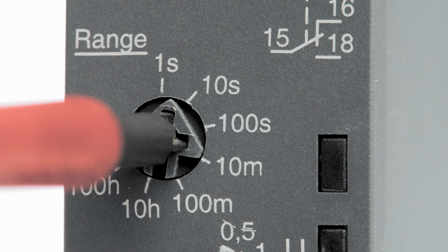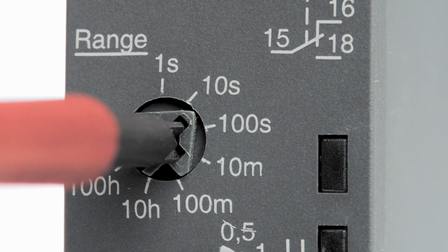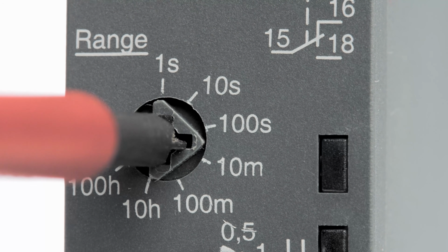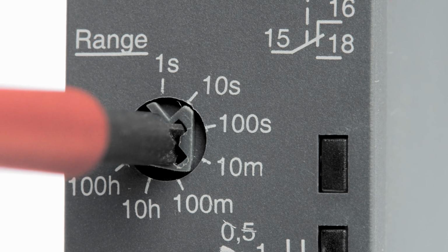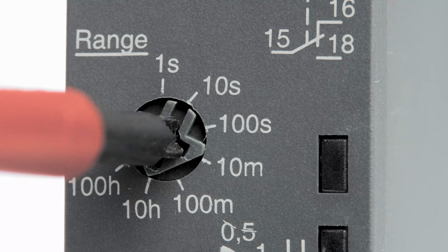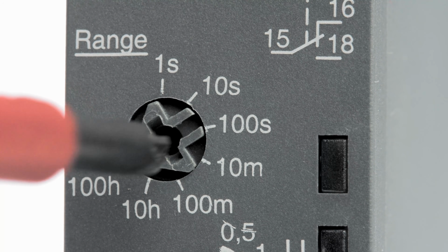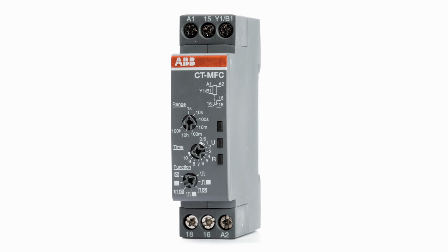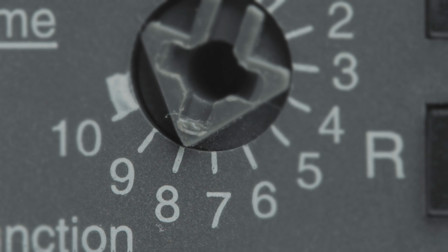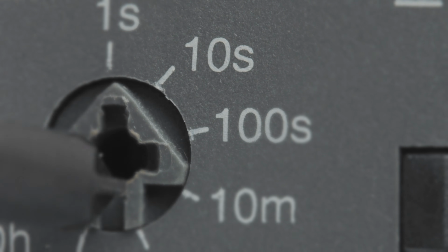Select the desired time range using the range dial. The printed values, 1 second, 10 seconds, 100 hours, represent the maximum value for each range. Choose a range where the final time fits comfortably. For example, for a required time of 8 seconds, select the 10 seconds range.